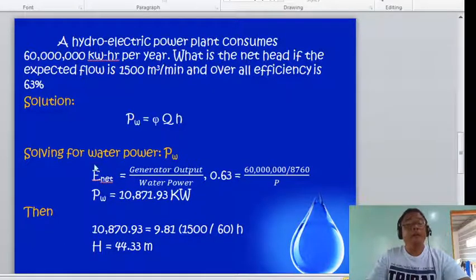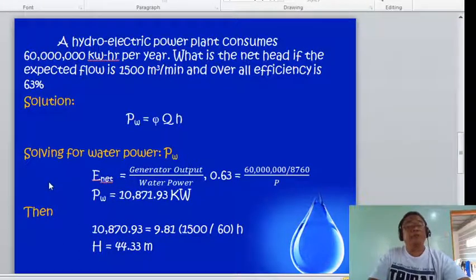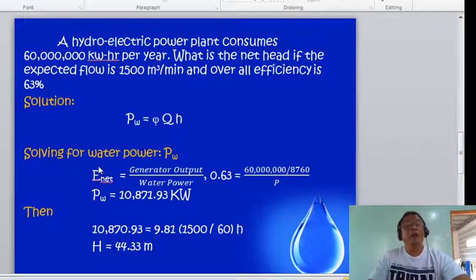Substituting from the formula: 10,870.93 equals 9.81 multiplied by 1500 divided by 60, multiplied by the head. The net head is 44.33 meters.